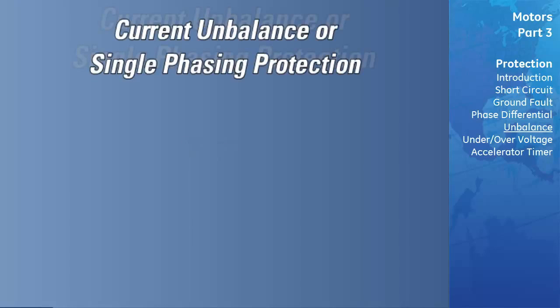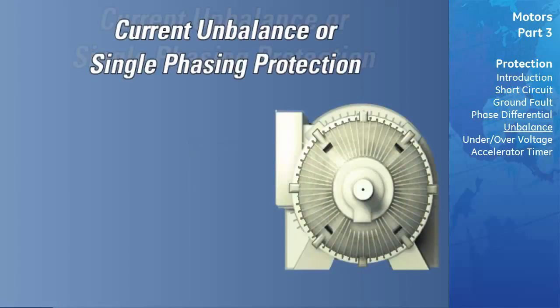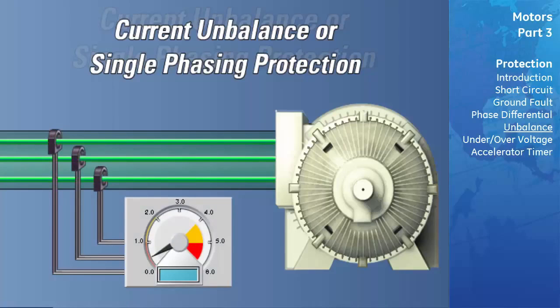Current Unbalance or Single Phasing Protection. The contribution of current unbalance to thermal capacity was covered earlier. Here, the magnitude of the current unbalance is used to detect and trip the motor if a single phase condition occurs. Single phase refers to the situation when one of the three phases is no longer being supplied to the motor. If enabled, a trip and/or alarm occurs once the unbalance magnitude exceeds the current unbalance trip pickup for a period of time specified by the current unbalance alarm trip delay.